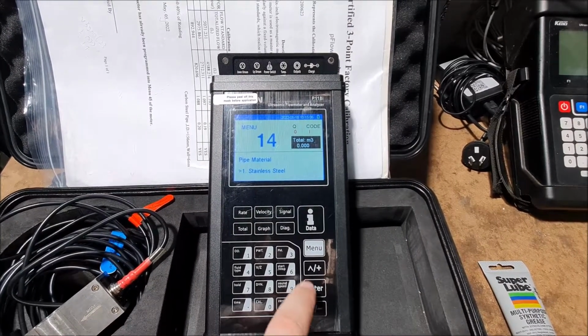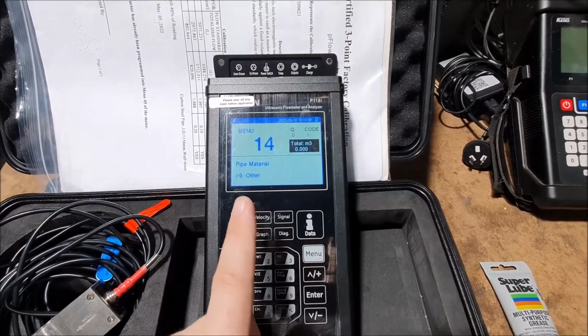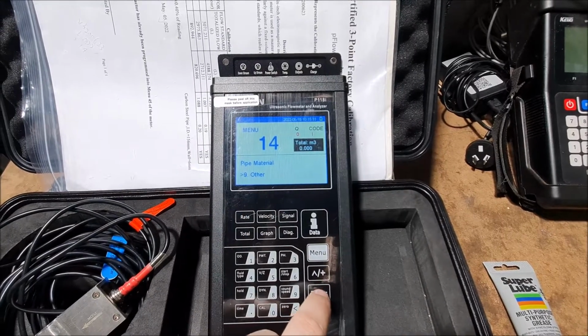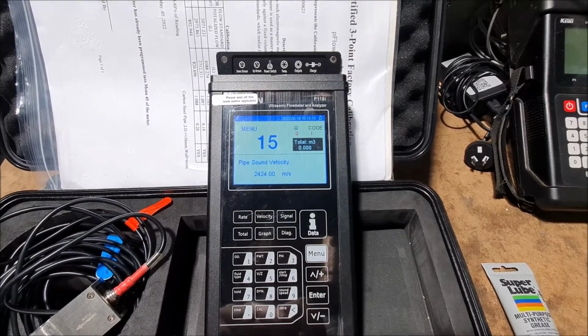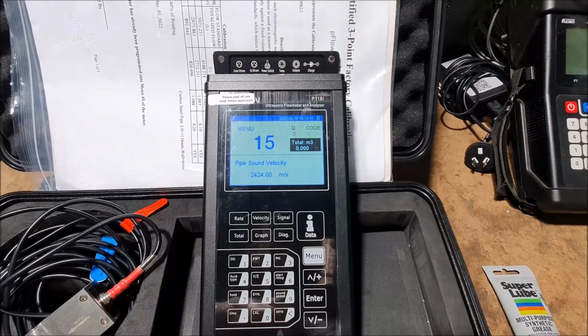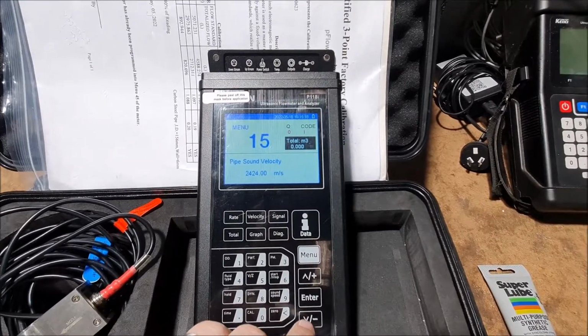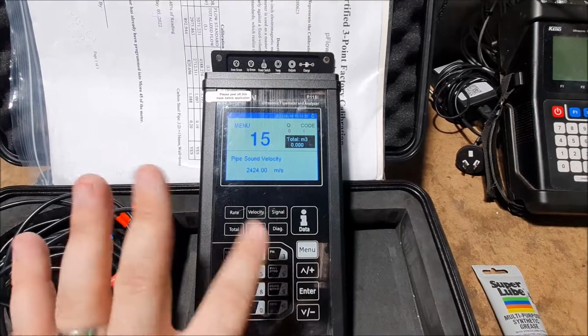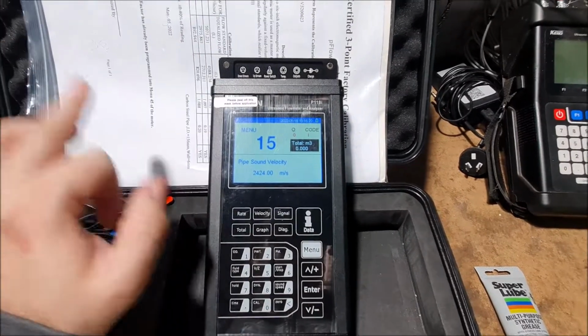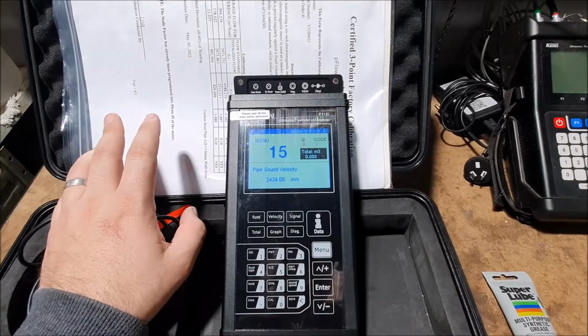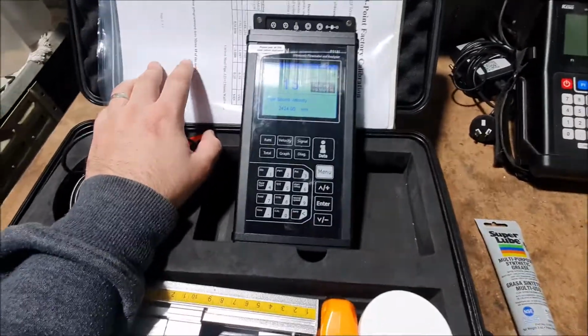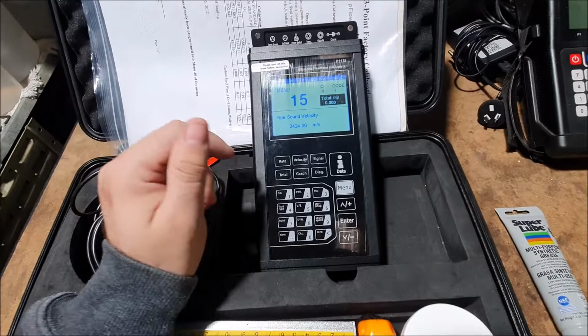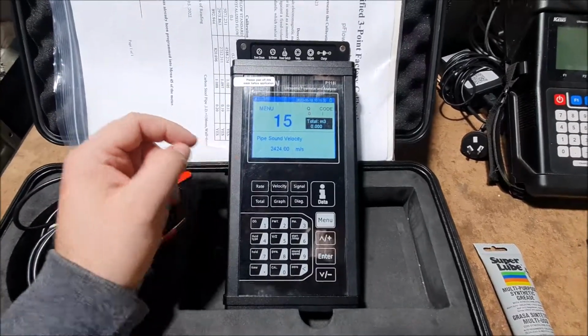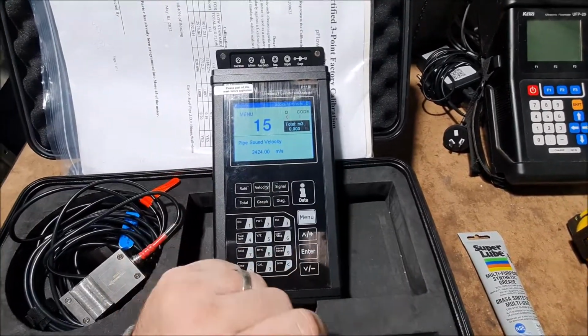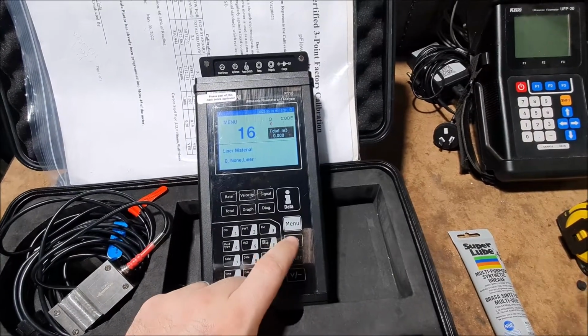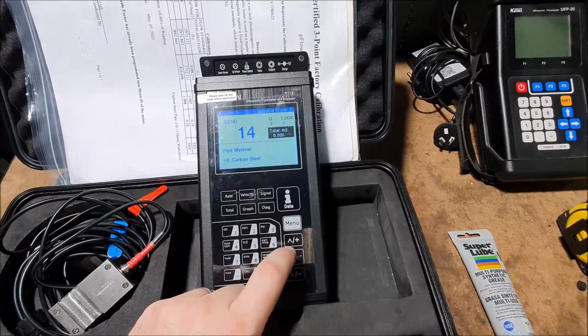Okay, and if your material isn't one of those listed here, just select other, and then you'll see the next menu will unlock where you can input the sound velocity of your pipe material. So you just press enter and manually enter that in. There's some other materials in the manual, which you can check in the manual, or maybe with a web search you might find your particular material and then manually enter the sound velocity. But in this case we're just going to select here carbon steel.